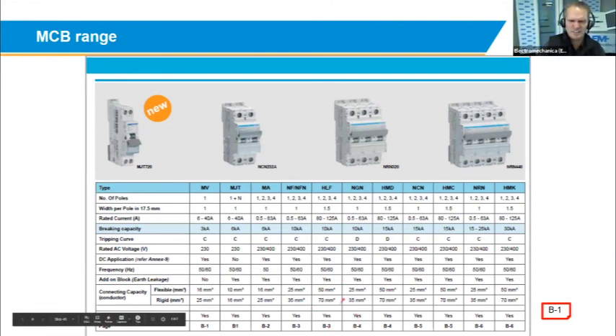I have just some technical information. Can it accept an add-on earth leakage device? And can it be used in DC applications? Then you can always go back to the table at the back. And then this is the width of a module. So it's 17.5 millimeters wide from one side to the other side. The bigger ones, the 125 amps, are 1.5 modules wide. So it takes up a little bit more space, but you can go up to 125 amp in a miniature circuit breaker.